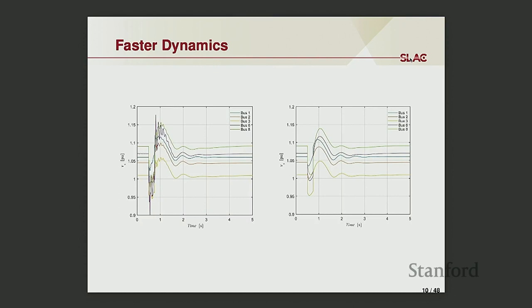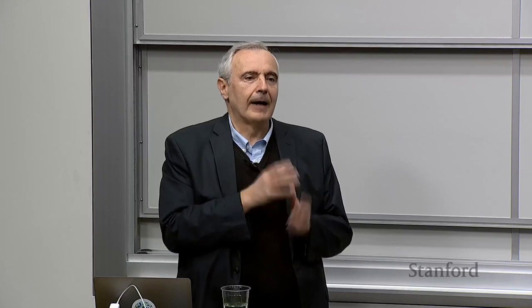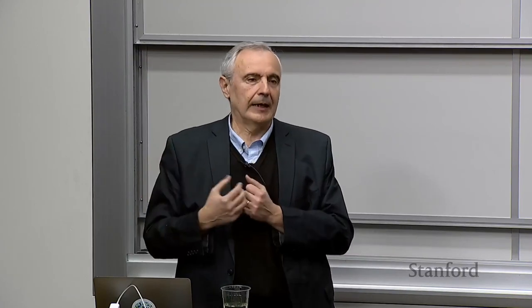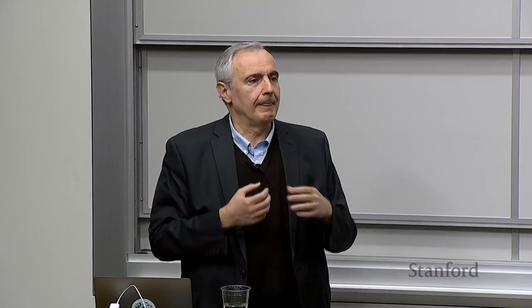Also, the transients of these new sources are largely determined by the settings of controls. In other words, control has much more authority than it used to have in the old electromechanical system, which is both good and bad. It's good because there's hope of achieving responses we couldn't achieve before. But it also means that if we set it wrong, we'll get instability more often. So that's coming our way.